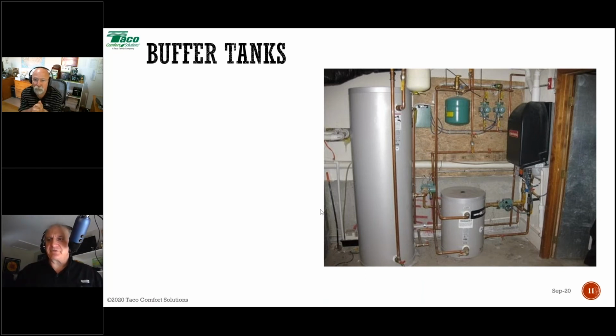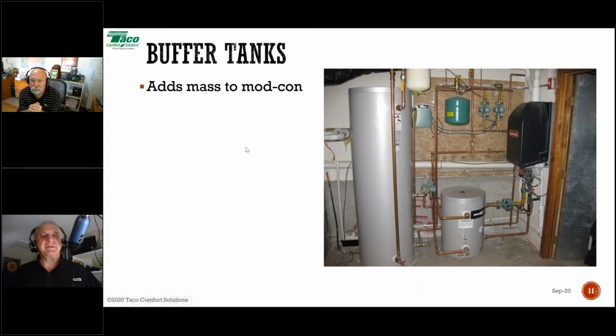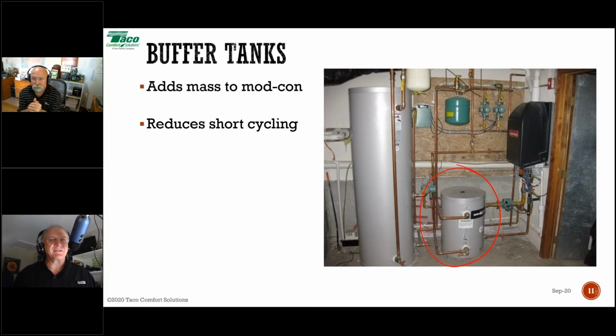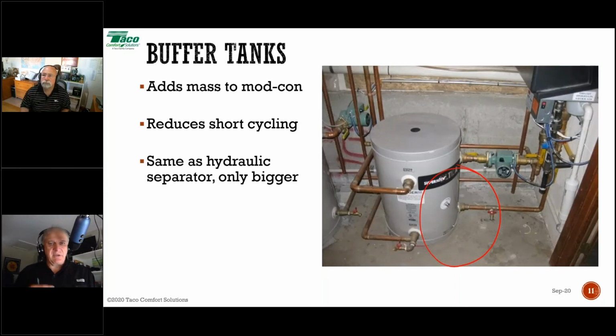I want to leave you, because we just got a few minutes left, with buffer tanks. Buffer tanks kind of go beyond the hydraulic separator. A buffer tank's just a big honking hydraulic separator. It's this thing right here. It's a big hydraulic separator that adds water content or mass to a mod con to reduce the likelihood of short cycling when we have what we call microzones, when the load of the smallest zone is significantly lower than the lowest firing rate of the boiler. Okay, you pipe it up exactly the same way as a hydraulic separator. It just has more water content.